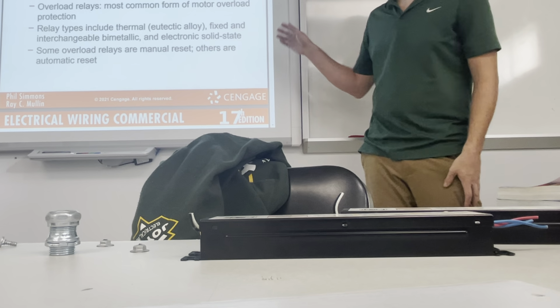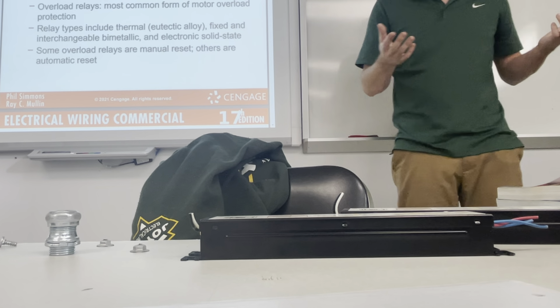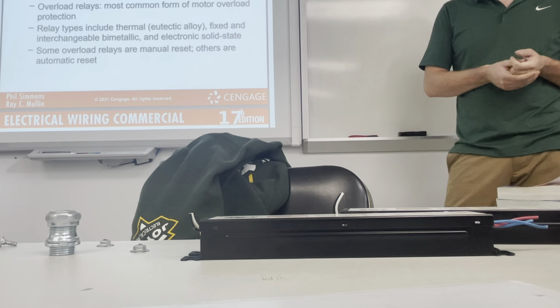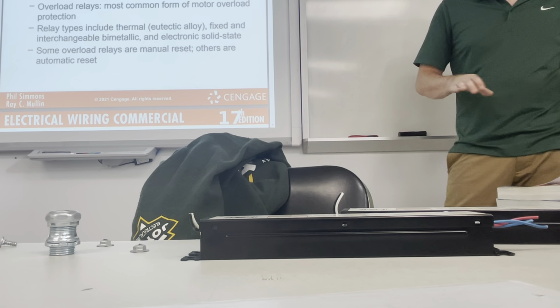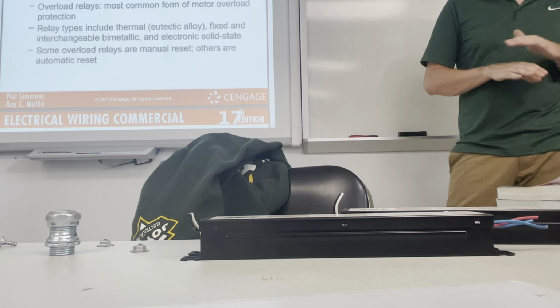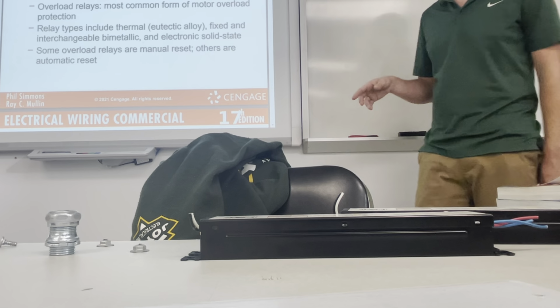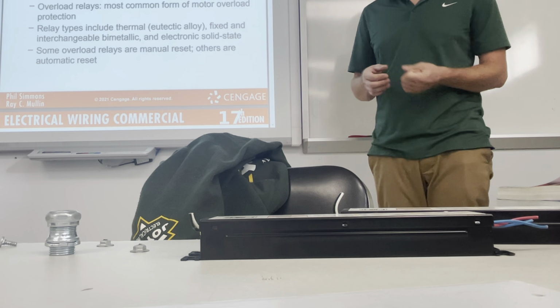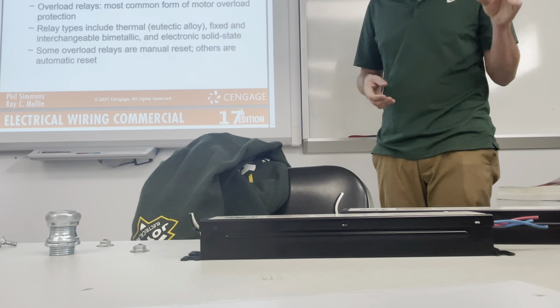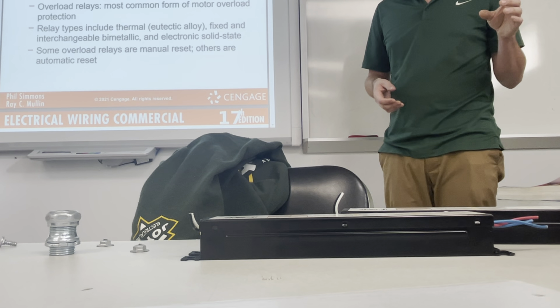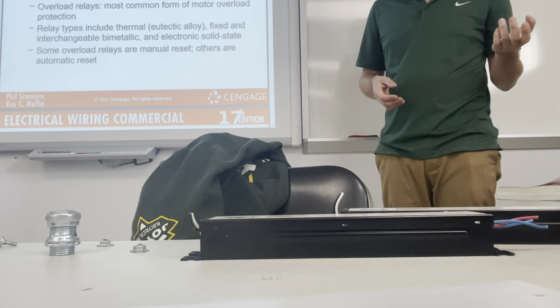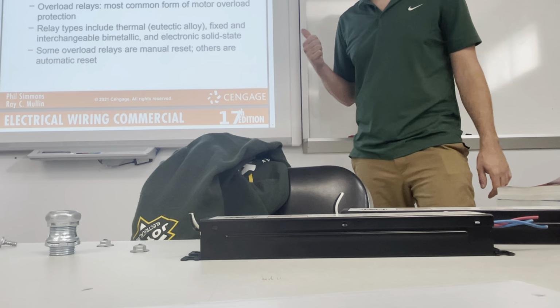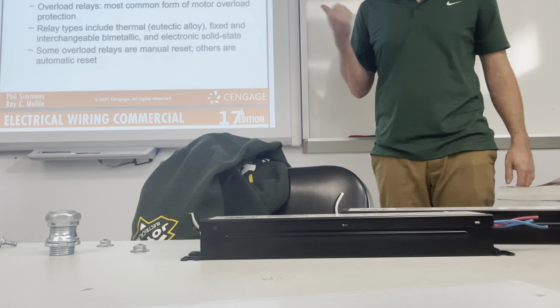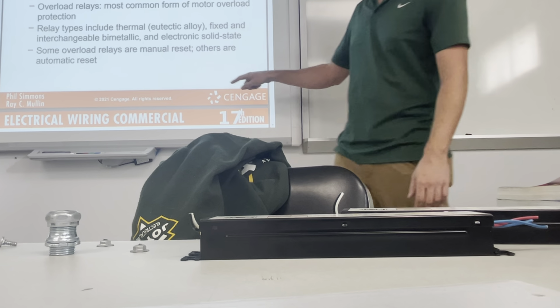So once again, it's kind of like a circuit breaker. It's a circuit breaker of the motor, but it does not care about amperage or voltage. It only cares about heat because that's what's most detrimental to an electric motor. You heat a magnet a lot, what's going to happen to it? It's no longer going to be magnetized. Well, same thing with our motor. If we overheat our motor, that motor is going to be useless. So it's the exact same theory.